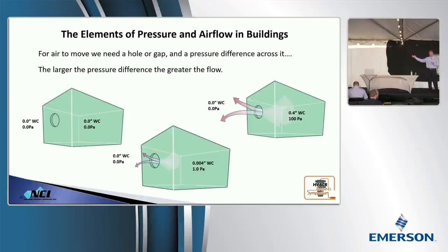Now the first, because you're going to go, Dave, this is too simple, we know this stuff. And that's right, you do know this stuff. But once again, it's that 90-degree shift to look at things a little bit differently, through a different set of lenses from a different angle, and apply what we know to combustion air. So, how many of you guys know this? If you have an opening, it takes a pressure difference for flow to move through that. That's one of the most basic principles of airflow. Everybody in this room knows that, right? So whichever side has the higher pressure difference, it will drive air to the other. Mother Nature loves balance. She will rot a building, and she will kill a family to get it.